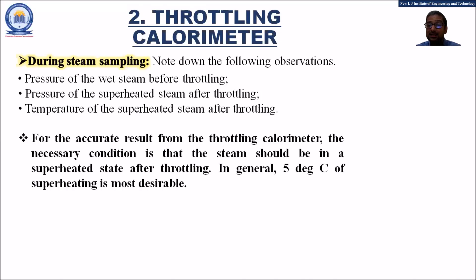Hence the statement is written: for an accurate result from the throttling calorimeter, the necessary condition is that the steam should be in the superheated state after throttling. Generally, 5 degrees Celsius of superheating is most desirable. That means the wet steam temperature must be increased by plus 5 degrees Celsius. So these are some of the practical concepts, the observations to be taken during the steam sampling.